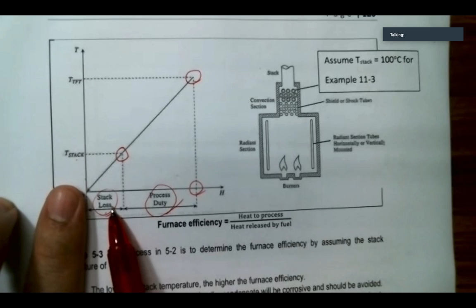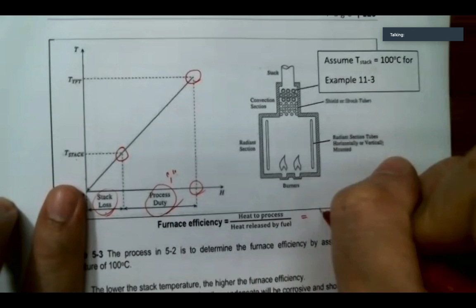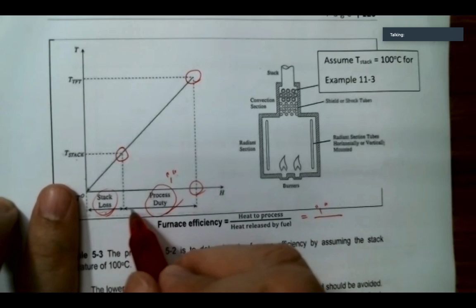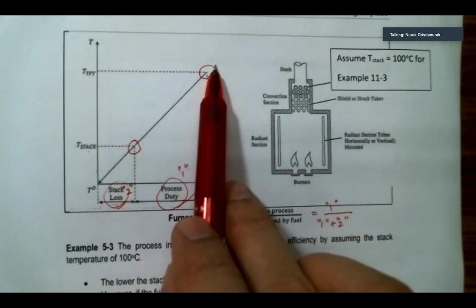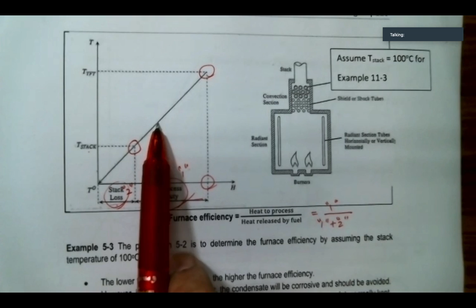So what can I do with this? I can calculate the furnace efficiency, right? Efficiency equals the heat to the process, region 1, divided by the heat released by the whole thing, so it is 1 plus 2, right? This is very common for calculating furnace efficiency: finding the temperature at the flame and the temperature at the stack, and then just drawing the line. However, you have to meet the pinch point. If you hit the pinch point, your furnace efficiency will be the highest. You cannot go higher than that.